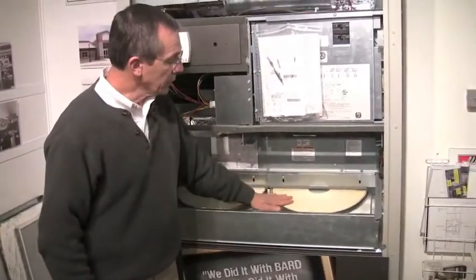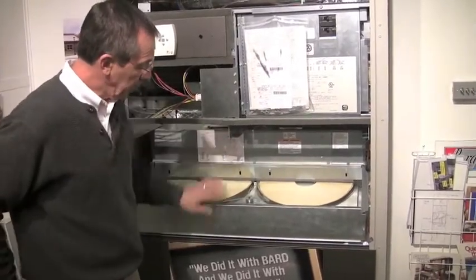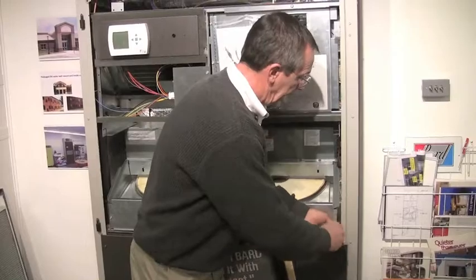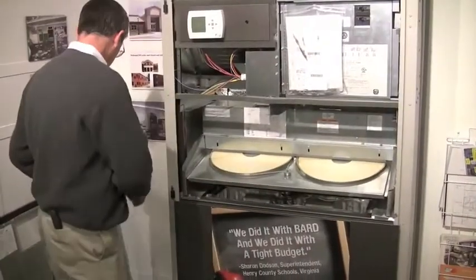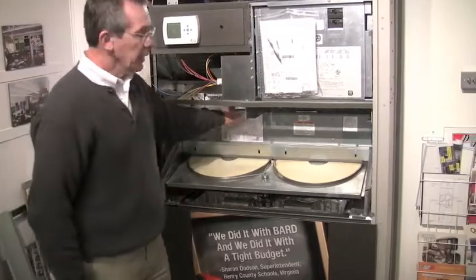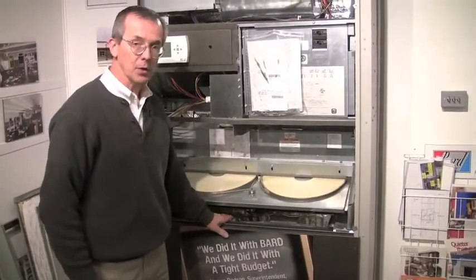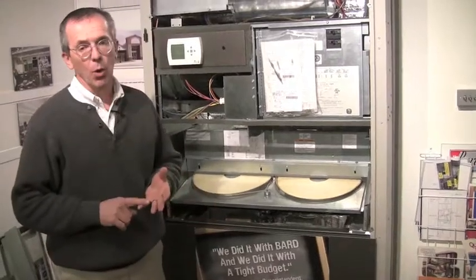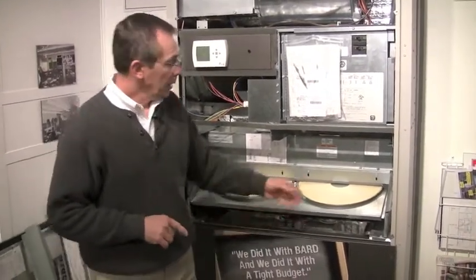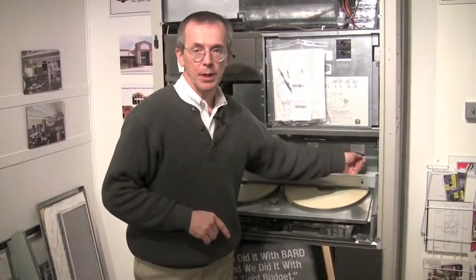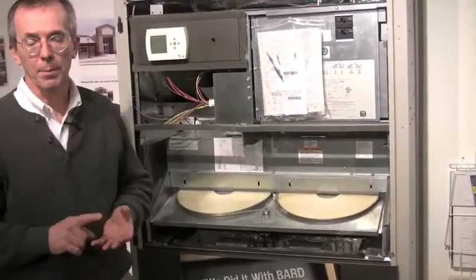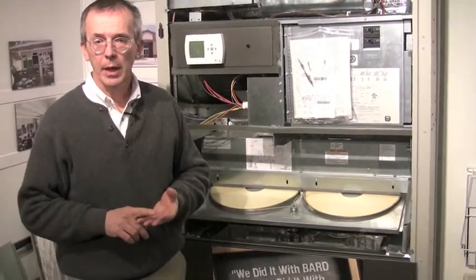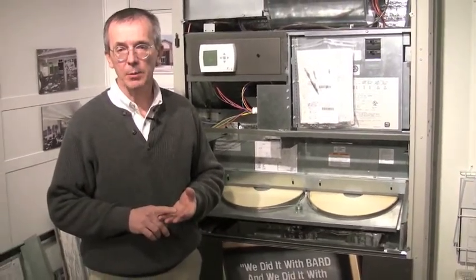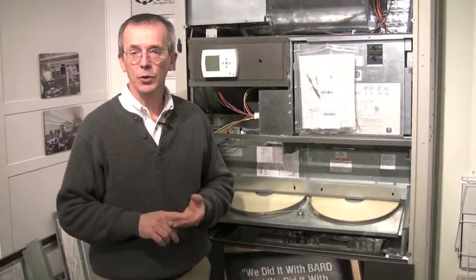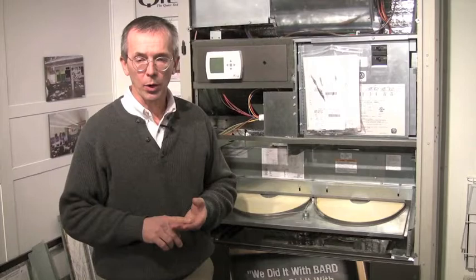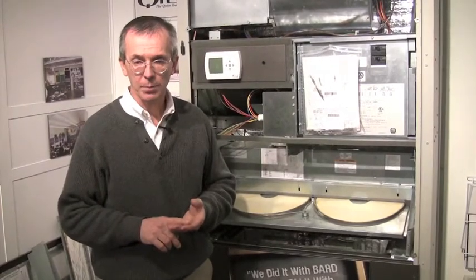The energy recovery wheels. This is the intake blower, and we have an exhaust blower behind this panel. Again, the intake blower and the exhaust blower. Each blower is 3 speeds. Behind this panel here are push pins to change the speeds of the blower from high, medium, or low. High speed is 450 CFM, medium speed is 375, low speed is 300. Each blower can be controlled with either of those speeds.